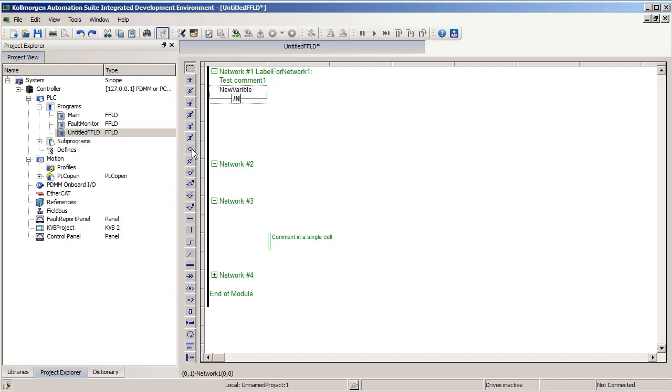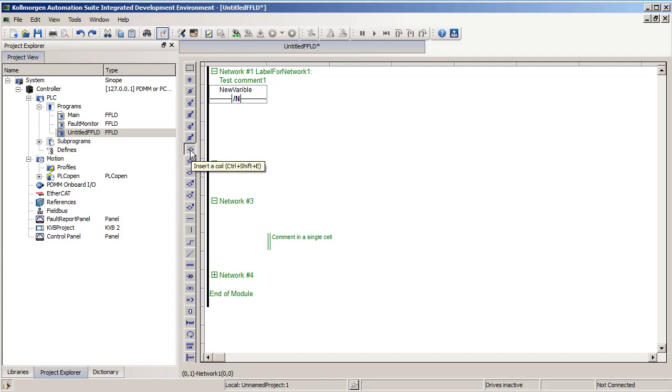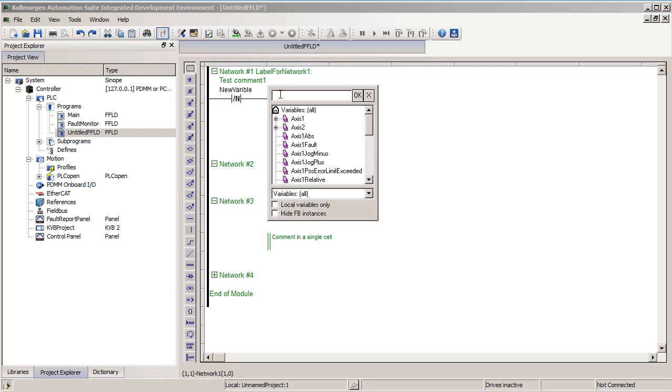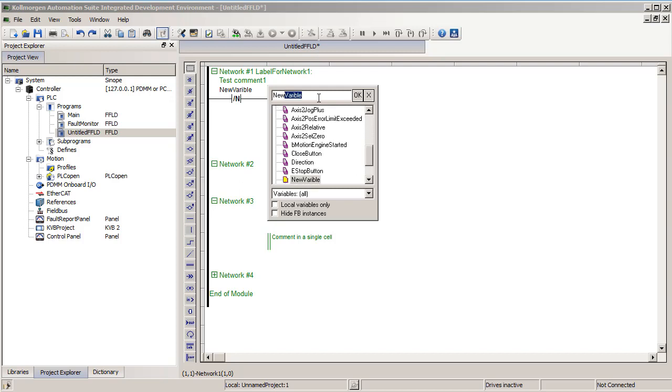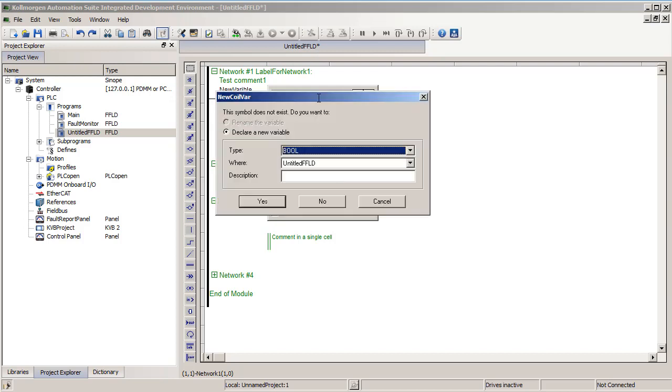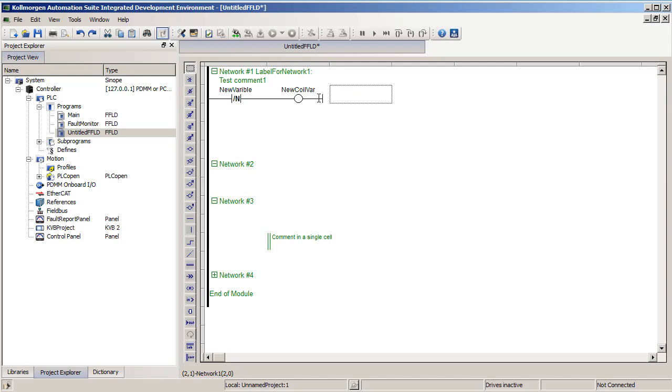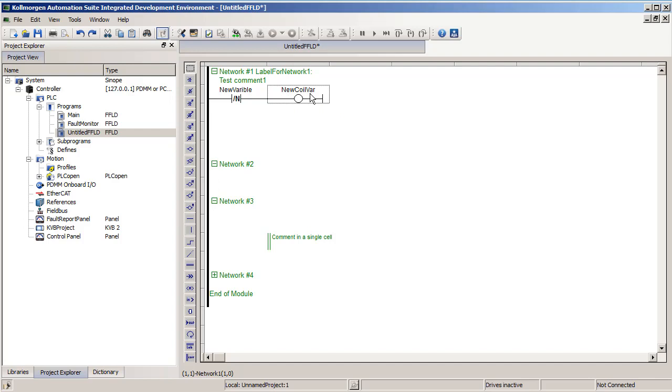We also have six different coils you can add to your ladder programs. You add them in the same way as you do contacts. You choose the one that you would like, then click on it, or as you see as I hover over a button it will give you the keyboard shortcut. Power users may memorize these to be a little more efficient. Once you have one selected, you can drop it into your program, and the same pop-up window will come up with a list of all Boolean variables in your program. I am going to create a new one. Coils act as outputs in the ladder world. So with this standard coil, when power is flowing to it, it will make the assigned variable, in this case new coil var, true.